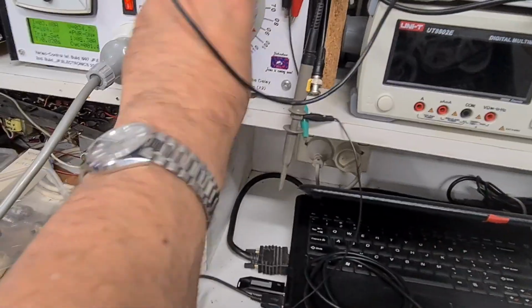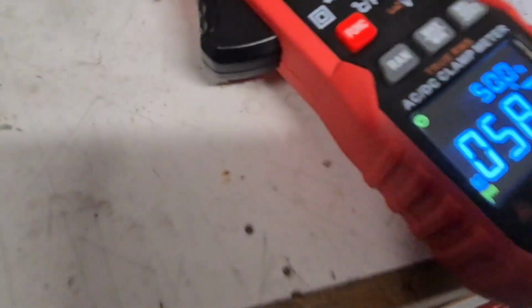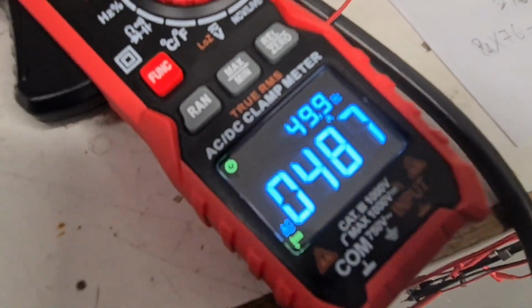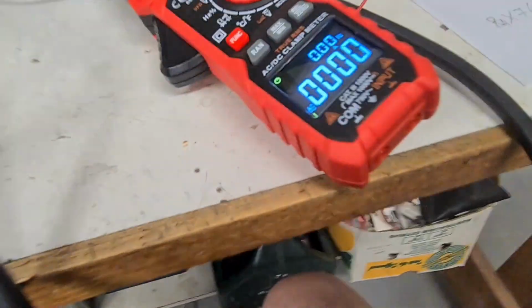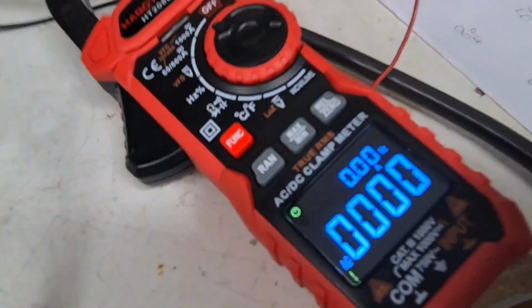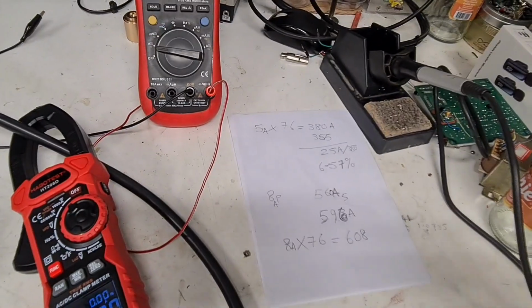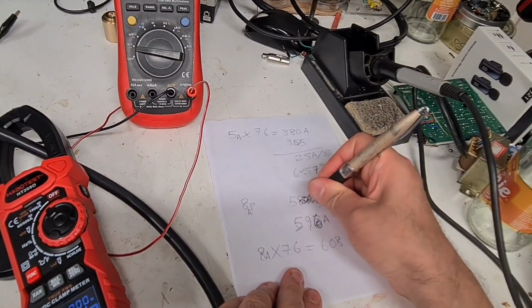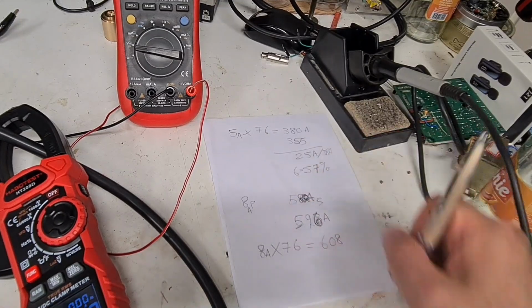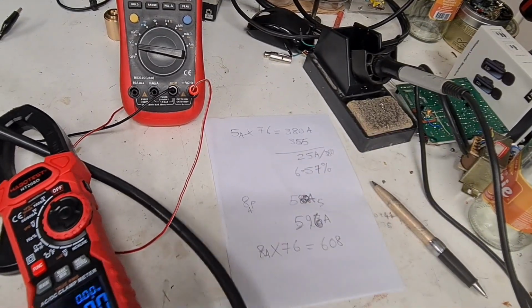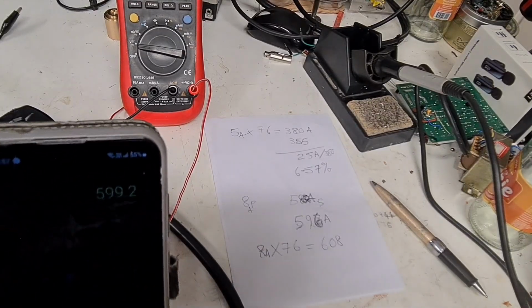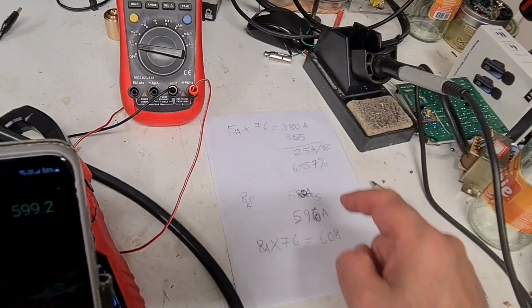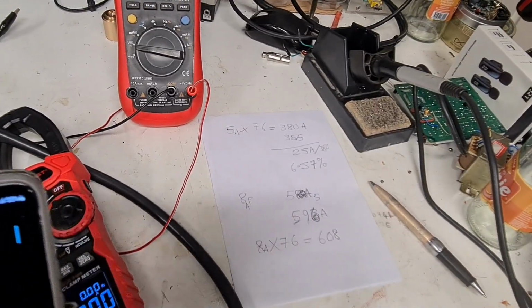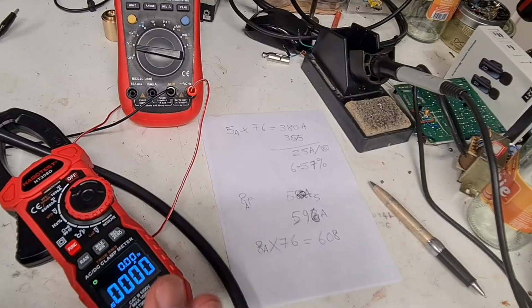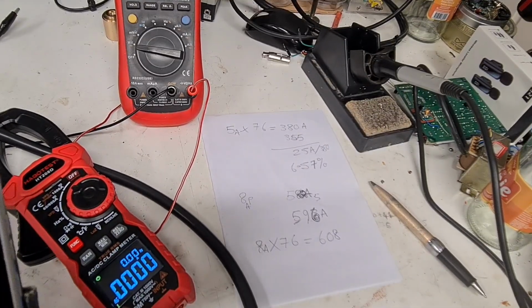8 amps, yep. 582. 582 is what I read. That's because the wire is getting pretty hot here. So it's 582, you see? So let's start again. Sorry. With the formula, let's change this 582 at 8 amps. The longer I keep it, the wire is heating up, the resistance is going high, and therefore it's creating a voltage drop, which means the ratio is changing. So I'll have to measure the first current when I first start it while the wire is still cold. Okay, that's the true figure.